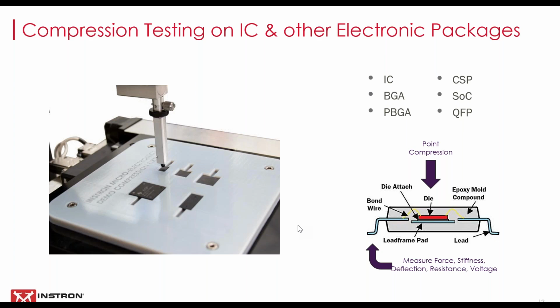This fixture design is an example of how a good fixture can contribute to improved throughput and repeatability. Rather than supporting identical specimens, this fixture holds 5 structures of different sizes that are each subjected to compression at 5 points for a total of 25 tests. The use of this fixture with the XY stage ensures the test points on each chip will be consistent from one sample to the next.